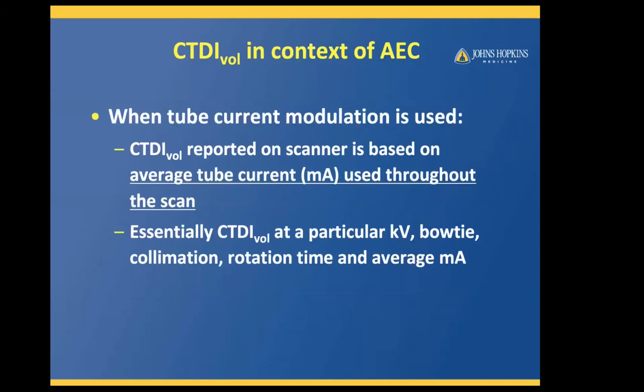So when we're getting this dose report, if the protocol uses automatic exposure or tube modulation, the CTDI volume reported is an average value of all the slices, based on the average tube current used throughout the scan. Essentially, the CTDI volume depends on the kV, the bow tie, collimation, rotation time, and then average mA.